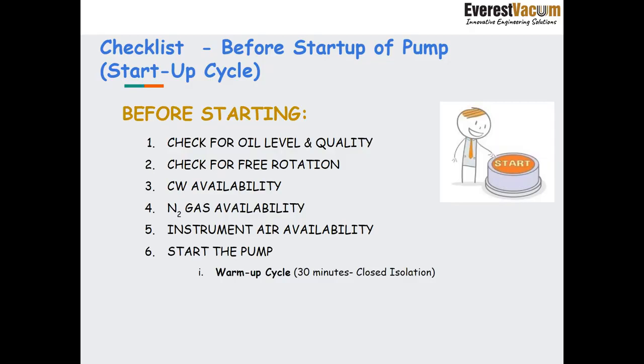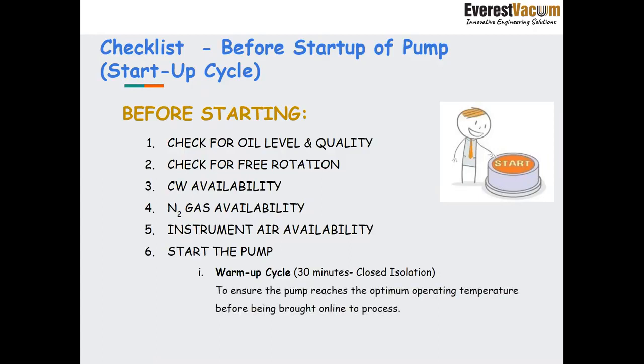Then the programmable logic controller comes into play, wherein the pre-fed program will automatically start, and there will be a 30 minutes warm-up cycle. The isolation will be closed and the pump will start operation. And why is this warm-up done? It ensures that the pump reaches an optimum temperature level, because if it is too cold, there is a very likely possibility that condensation would take place inside the pump. So this warm-up cycle for 30 minutes ensures that the pump comes to an optimum temperature. It is neither too cold nor too hot.